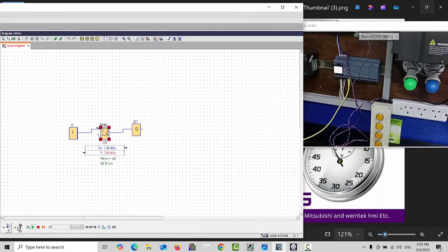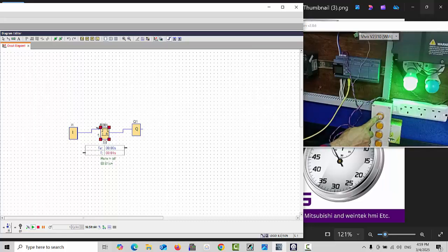And if you would like to test here in the simulation mode, you can also. When you click I1, this timer is running. You can see after 3 seconds this is on. Again I will check, see, as 3 seconds are completed, our output will be on. And if we select I0.1 here, just 3 seconds after it makes it on. See, now the time is 3 seconds.